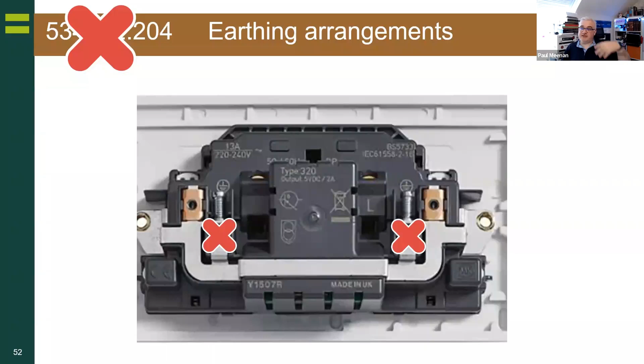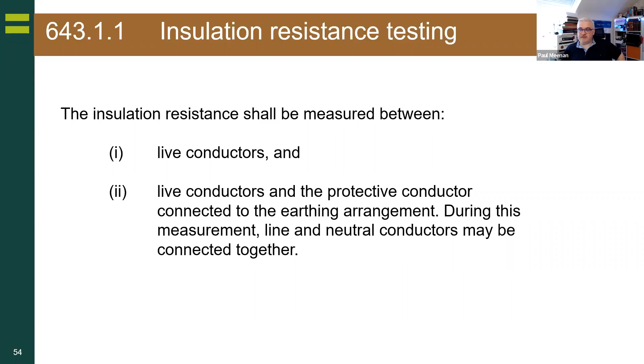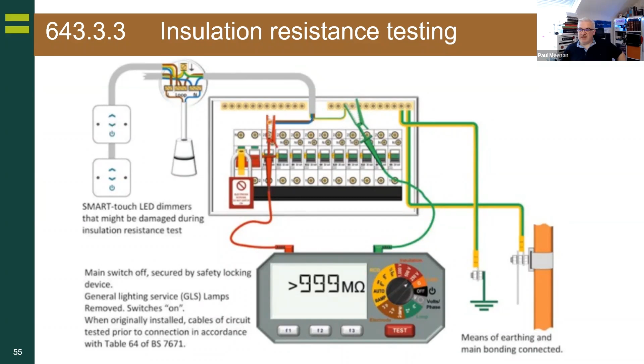Part 6, very controversial part. There's a requirement for insulation resistance. I'm not going to dwell on this too much, but in a nutshell, test it before you connect all the connected loads, and then afterwards you can join the live and neutral together at a lower voltage, following the manufacturer's equipment. If you're looking at Guidance Note 3, there is some very good visual guidance. That's been pretty much a rewrite that informs you about smart equipment now, so there are more up-to-date images for us to use and learn from. But yes, make sure you do the insulation resistance test, and if you do it at 250, the requirement of 1 meg still stands, not 0.5. So that kind of covers that very briefly.